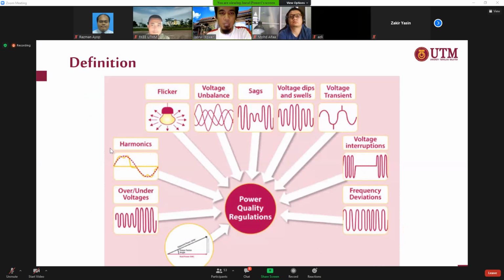This is several power quality problems you can see, not necessarily on solar but in our normal power system. This is the list: the first one is due to power factor — a power factor problem. Here is an under or over voltage problem. Here is a harmonic problem. Here is a flicker problem. Here is voltage unbalance, sag, voltage dip and swell, voltage transient, voltage interruption, as well as frequency deviation. This is some of the power quality you may have learned in class.